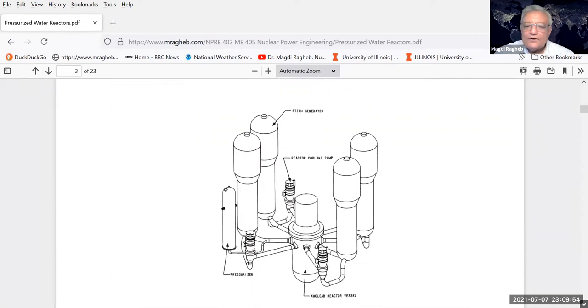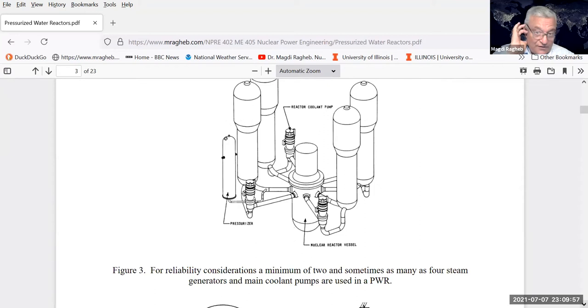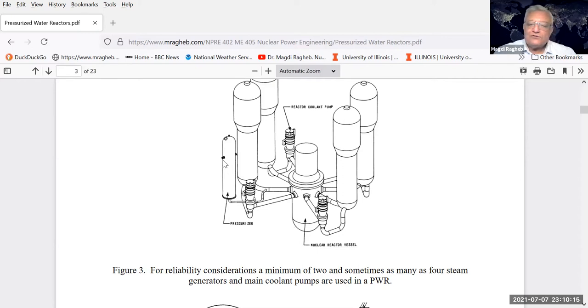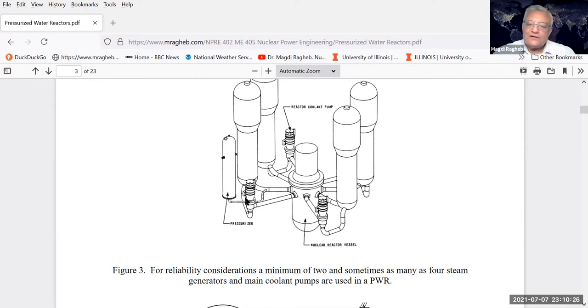For reliability and safety, a minimum of two steam generators is used, but this diagram shows four of them. In the case of the pressurized water reactor, the water is not allowed to boil inside the core by pressurizing it. You pressurize it using a device called the pressurizer - you produce a bubble of steam on top of the coolant, and that pressure distributes itself over the whole system. One of the steam generators may be put out of order for maintenance temporarily.